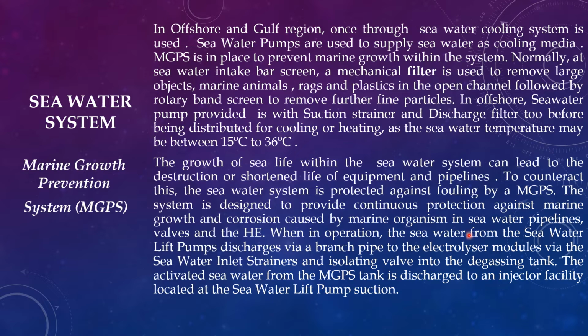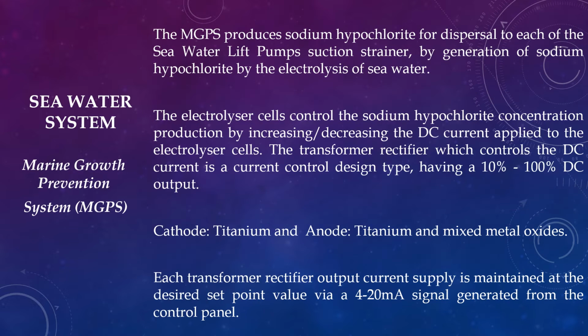When in operation, the seawater from the seawater lift pump discharges via a branch pipe to the electrolyzer module to produce sodium hypochlorite, via the seawater inlet strainers and isolating valve, into the degassing tank, also for shock dosing arrangement. The activated seawater from the MGPS tank is discharged to an injector facility located at the seawater lift pump suction, and the pump is started automatically. MGPS also will start, and the hypochlorite injection will be started to the pump suction. Now we can see how the MGPS system is working.